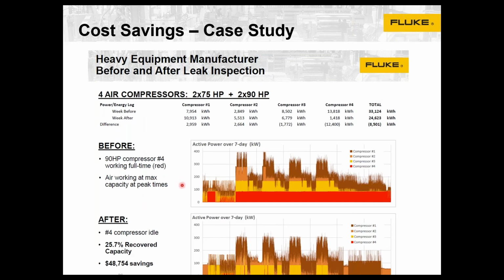So before, this is a kind of a map of what's being consumed and when it's being consumed. You can see that each of the different compressors are color coded as far as their energy consumption over time, when they're running, and essentially consumption. So you can see compressor number 4. That's really the one that we're looking at. It was called upon to run quite a bit, and that may have been a backup compressor. But what it shows is they're pretty much running all their compressors all the time, and this is the before case.